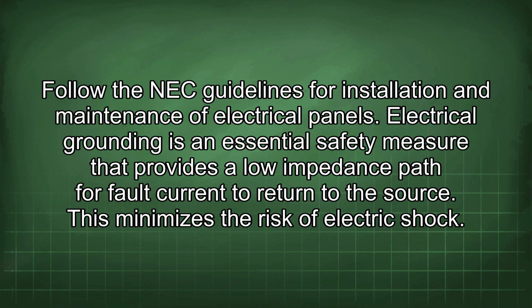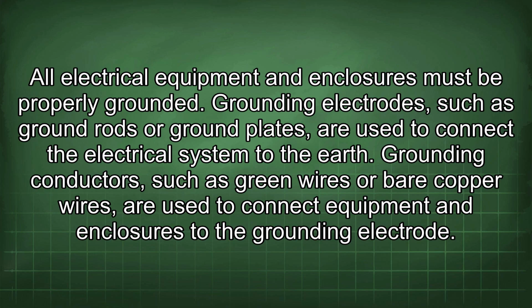Electrical grounding is an essential safety measure that provides a low impedance path for fault current to return to the source. This minimizes the risk of electric shock. All electrical equipment and enclosures must be properly grounded. Grounding electrodes, such as ground rods or ground plates, are used to connect the electrical system to the earth.